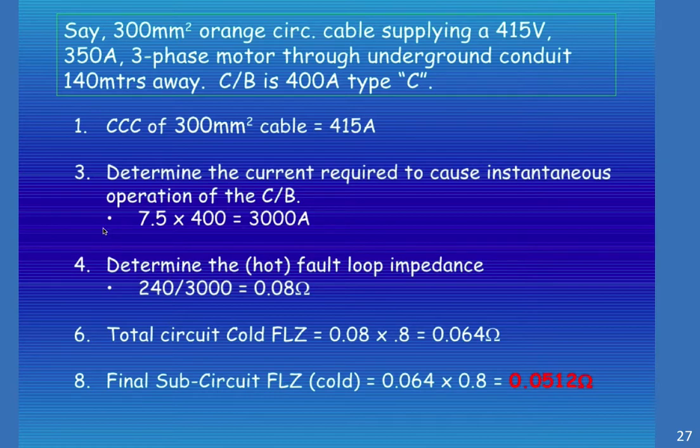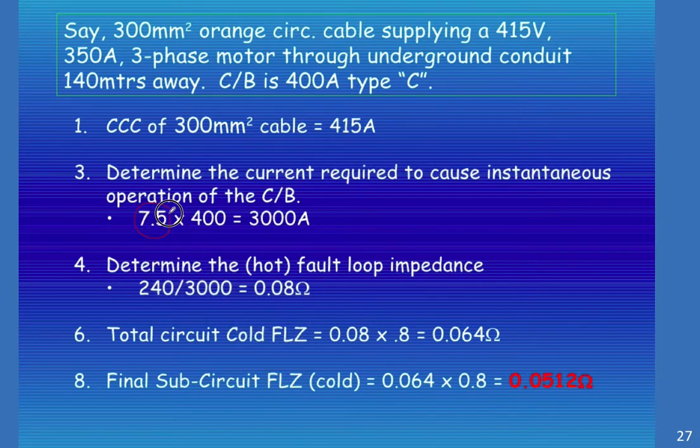We have to determine the current required to cause instantaneous operation of the circuit breaker. So being a Type C, we have to go 7.5 times. We know we've got 400 amps rounded up from 350. So 7.5 times 400 gives us 3000 amps to trip instantaneously.